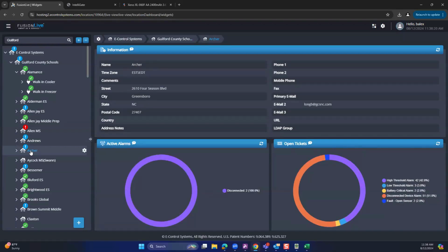So we can make them at each individual site. We can give users multiple sites, or we can have them get all sites. It's really up to how you guys want it laid out. But yeah, we can direct it to whoever it needs to go to. We can do it in a tree, so you guys won't get the alerts unless it's in alarm state for 15 minutes or 30 minutes or whatever it is, to give those area people or on-site people a little time to react to it before you guys even get alerted. We can do that too.